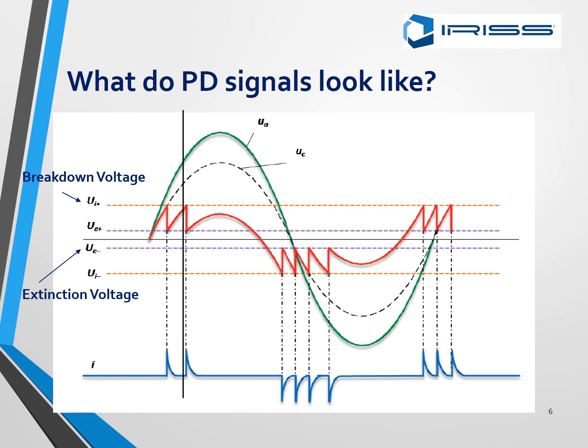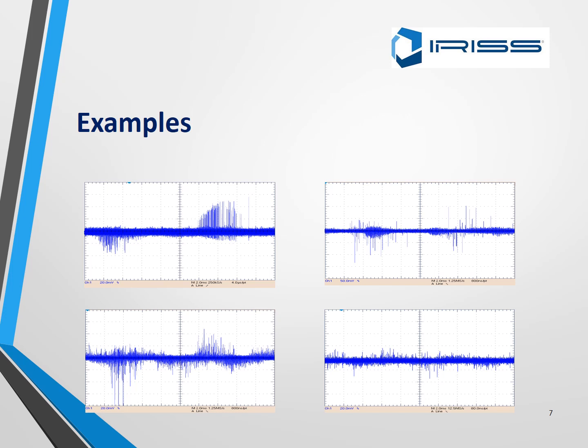When an insulator is subject to an alternating voltage, charge builds up within the void as the applied voltage increases or decreases. This causes a series of discharges with charge first moving in one direction and then the other. This results in PD having a distinctive pattern when viewed in the power cycle — this is what we call a PRPD. Here are some more examples of corona on different voltages of cabinets.